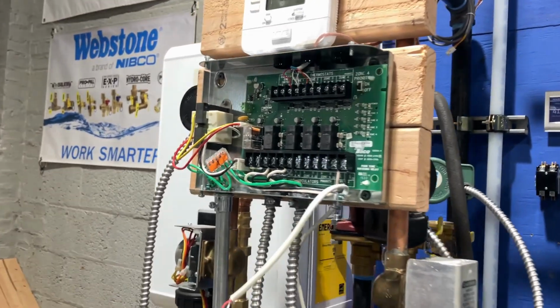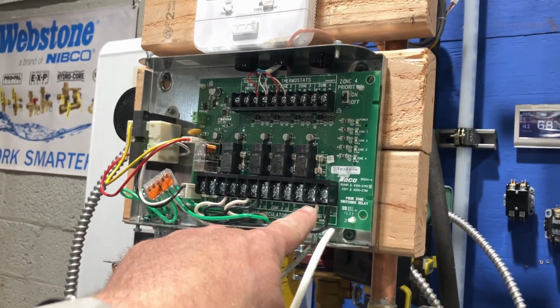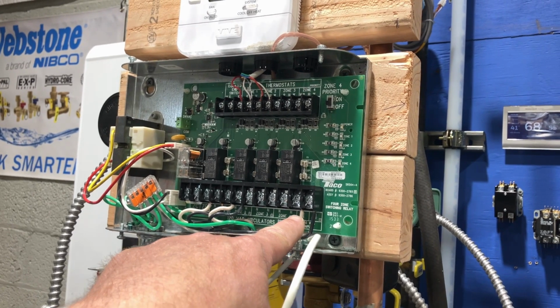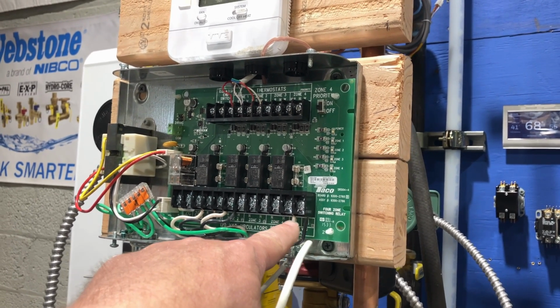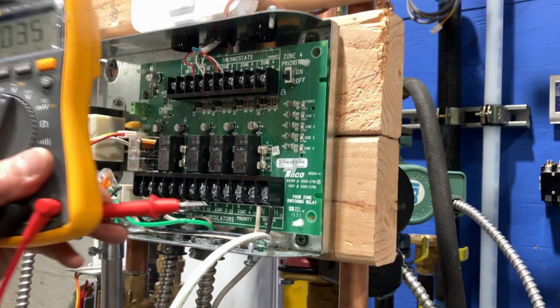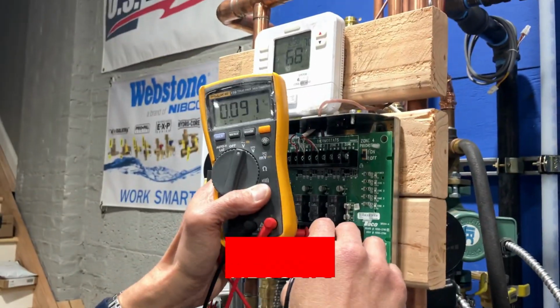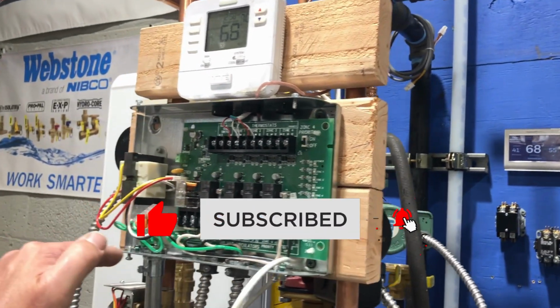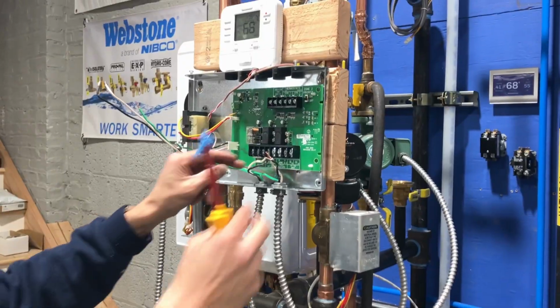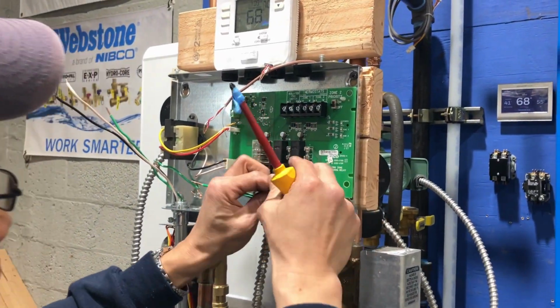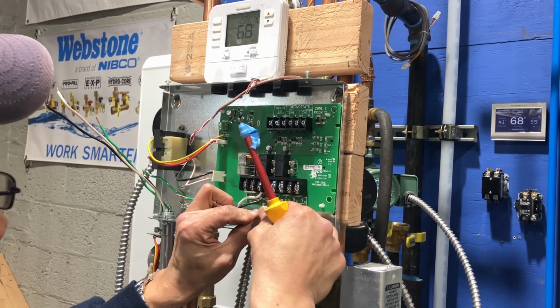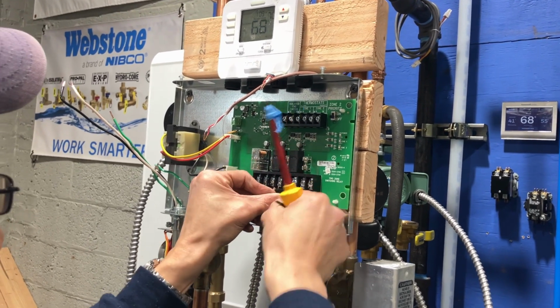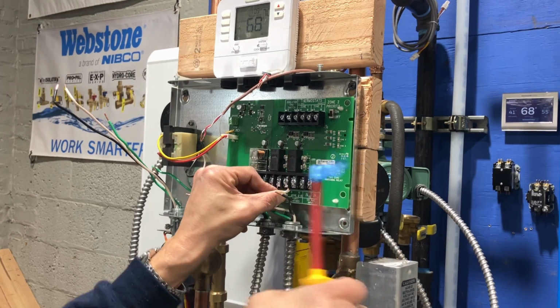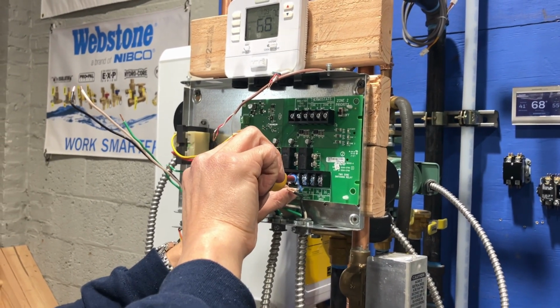So the first thing we're going to do, we're going to take our multimeter, we're going to make sure we don't have voltage at N and H, neutral and hot, of our 110 volt input. Okay, we have no voltage there, so it's now safe to proceed to remove all of the wiring, line voltage and low voltage from this control. All right, now the wires are going back, wire for wire, zone 1, zone 2, and then our 2 thermostats.